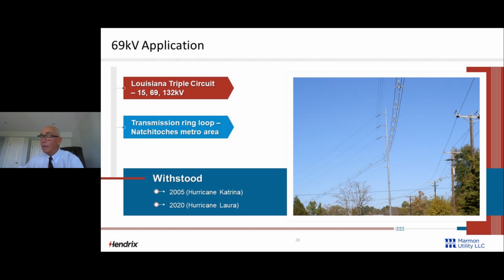Here's a Louisiana one. There's the city of Natchitoches, triple circuit. We had 132 on the top and 15 kV on the bottom. They framed this up for 69 kV bare wire. The line department said no. I think they said hell no. And they accepted spacer cable. So we got the spacer cable in here. This is a loop that's been around. As soon as we built it, it got hit by Hurricane Katrina. Survived. Had a couple of distorted spacers, but it survived. Never got shut off. And in 2020, it got hit by Hurricane Laura. So we're very, very happy with this, and so is the client.